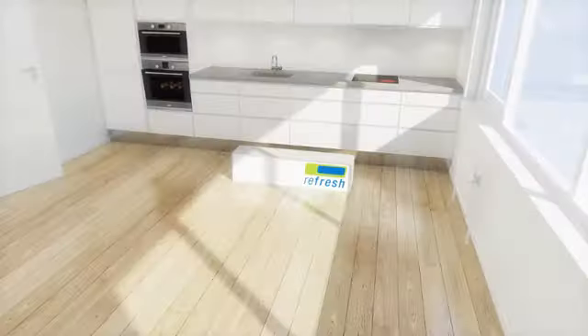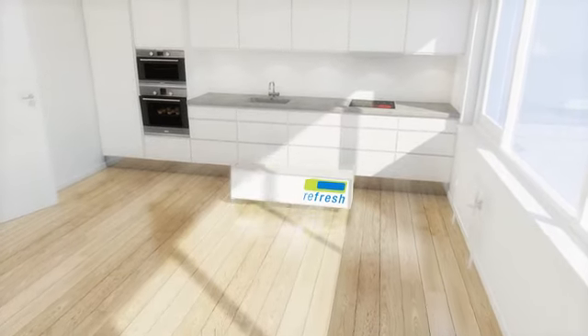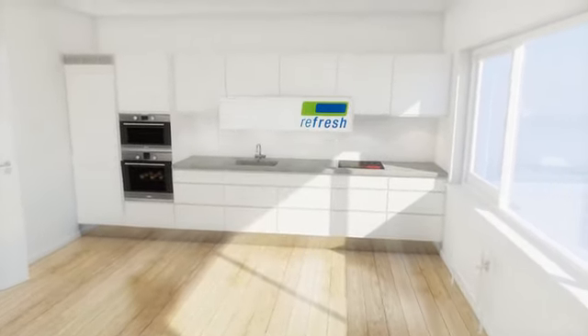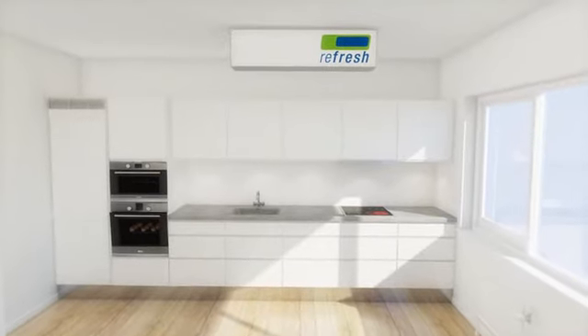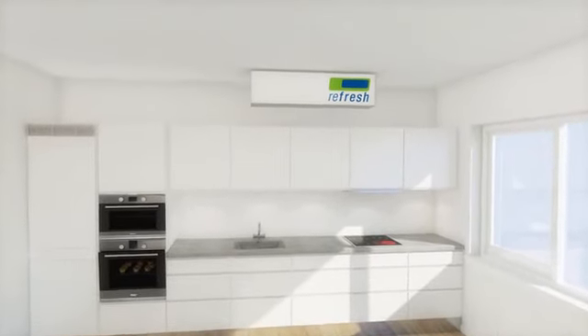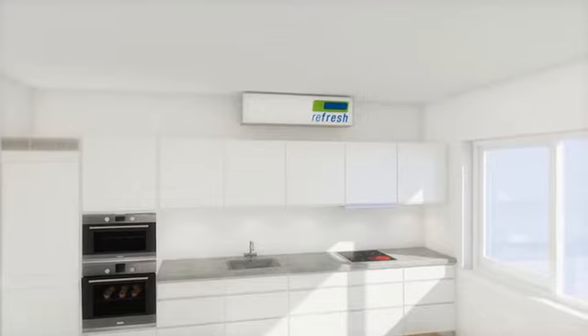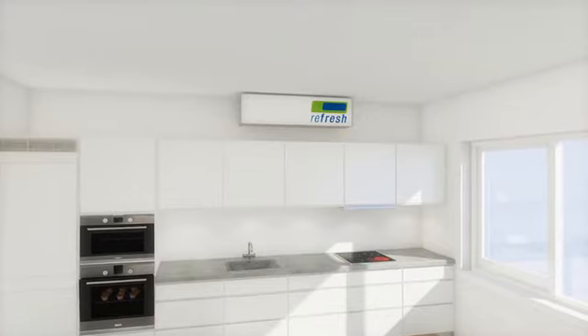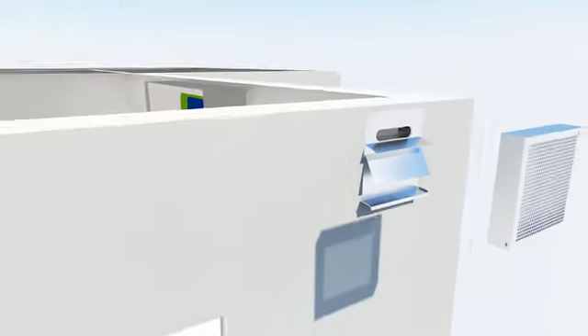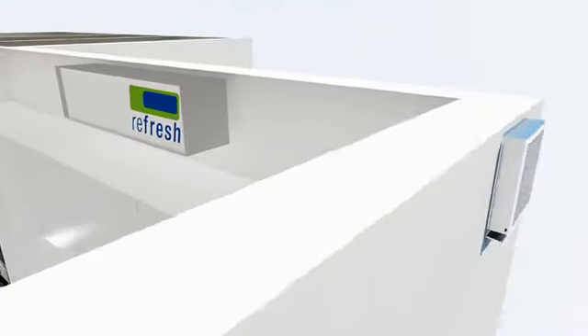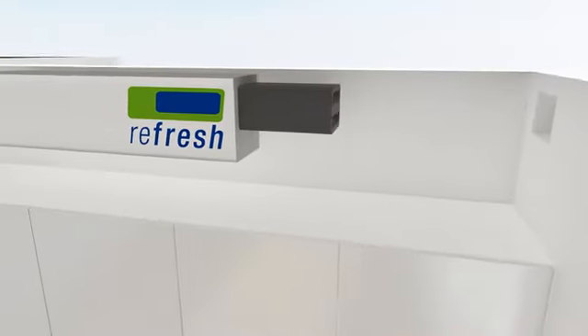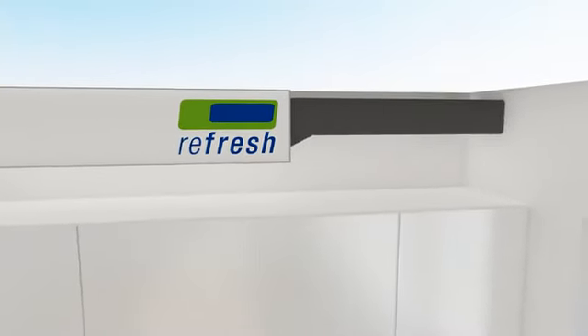The first step in installing the system is to position the air handling unit. In this example, the unit is installed above the kitchen cabinets. The air handling unit controls the ventilation in the flat and contains the heat recovery system. Holes are drilled in the outer wall to house the air intake and specially insulated ducts. The ducts are installed in the wall and connected to the air handling unit.